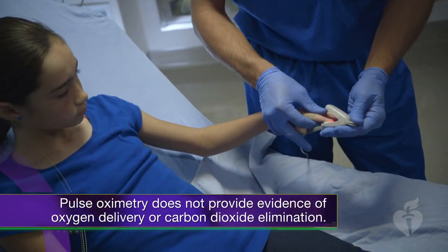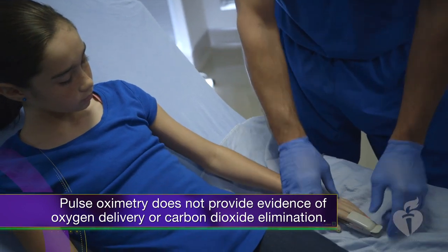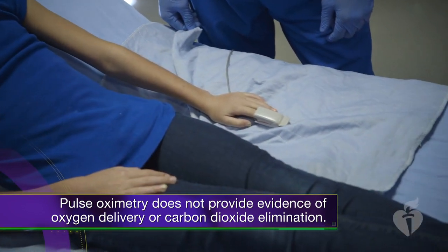Pulse oximetry generally gives an accurate estimate of hemoglobin oxygen saturation, but does not provide evidence of oxygen delivery. It also does not provide information about carbon dioxide elimination, which is referred to as ventilation. Now, during shock and cardiac arrest, systemic blood flow is severely compromised, and for a pulse oximeter to calculate the hemoglobin saturation with oxygen, it needs to detect pulsatile blood flow. If the child's pulses are extremely weak, the pulse oximeter may not be able to detect the hemoglobin saturation, or the results may be inaccurate.